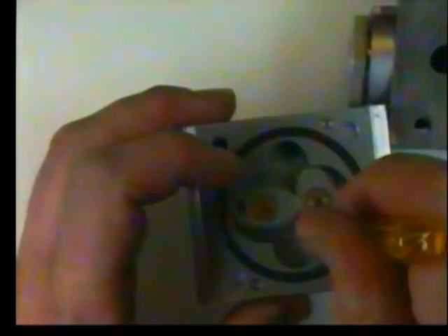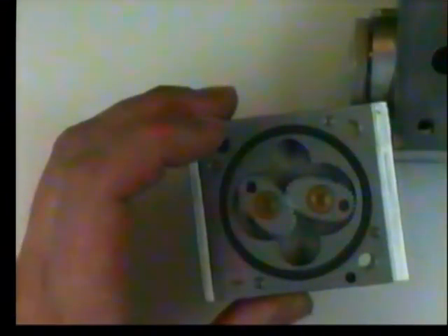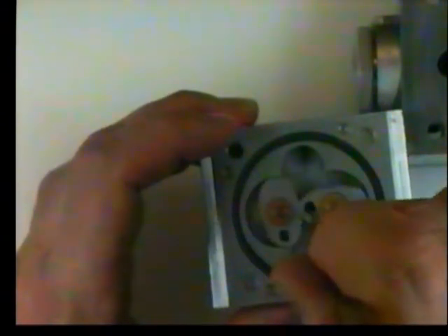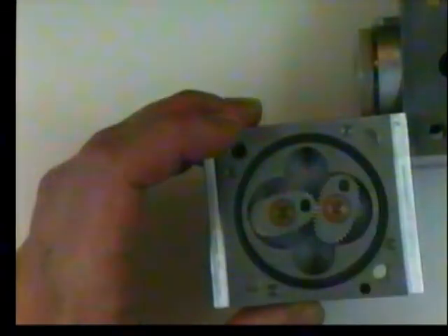Now if it's not too clear, don't worry, I'll be bringing this with me and we'll be able to see it in operation. But hopefully what we can see is that as the fuel flows through, we have a continual rotation motion. In this position we've trapped our little pocket of fuel. Now it's just been released through and can now escape out. This is a bit of precision mechanics. The amount of volume of fuel that is trapped in that area is a precise quantity.